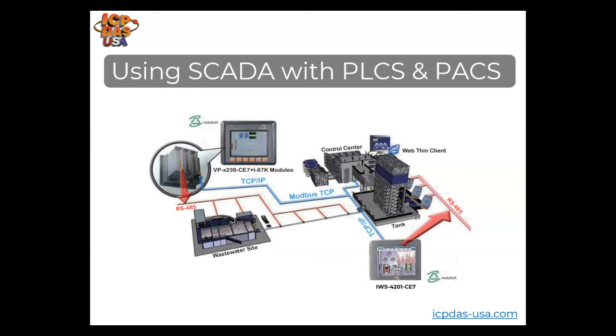SCADA software allows for monitoring of measurement levels like tank level, pressure, temperature, pH, and turbidity, and the visualization of those measurements on a screen. Data is passed over Modbus TCP or Ethernet cabling. I/O modules communicate over RS-485 as shown here.